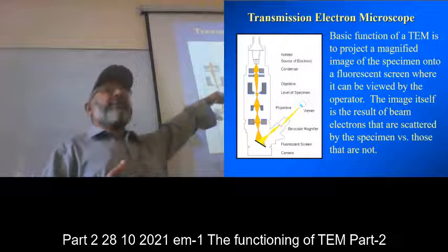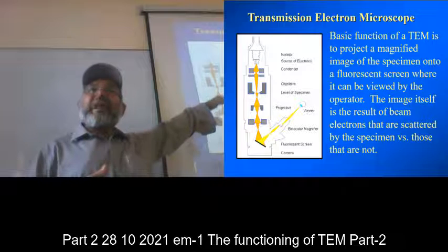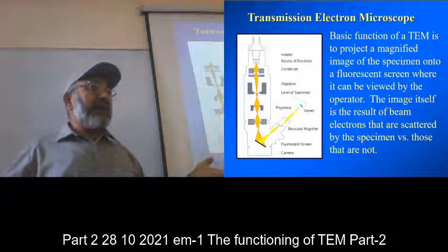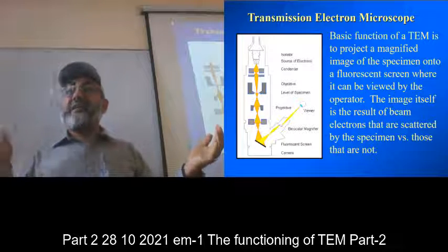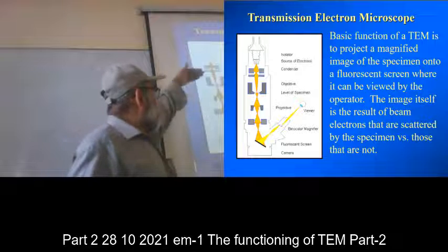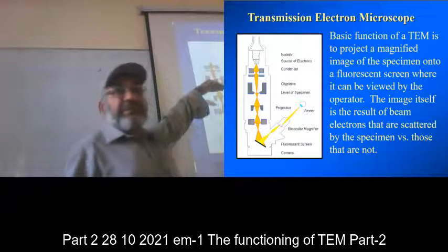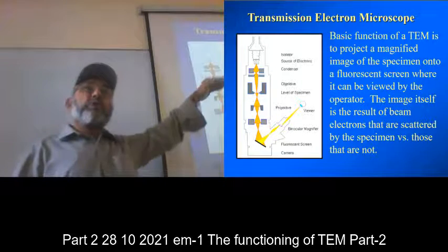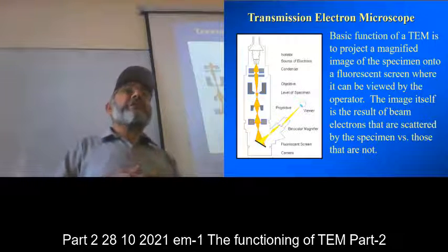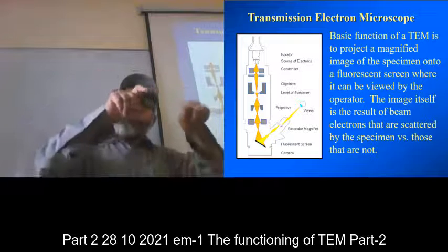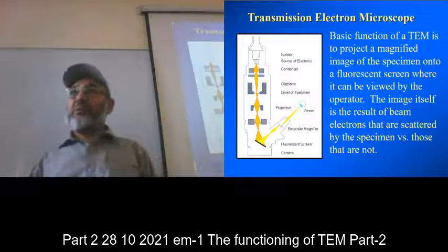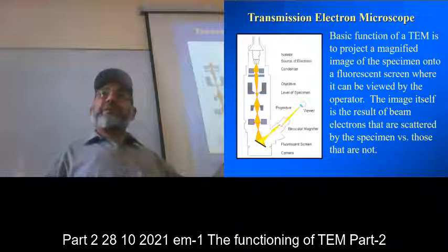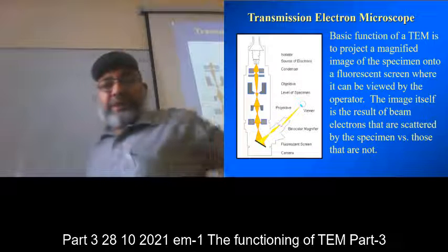So when they pass through the objective lens, again there is a chance of large angle scattering, and that large angle scattering is again dealt with by the objective aperture. There is an objective aperture after that. So whatever could not be focused onto the relevant area by the objective lens, is excluded by the objective aperture.